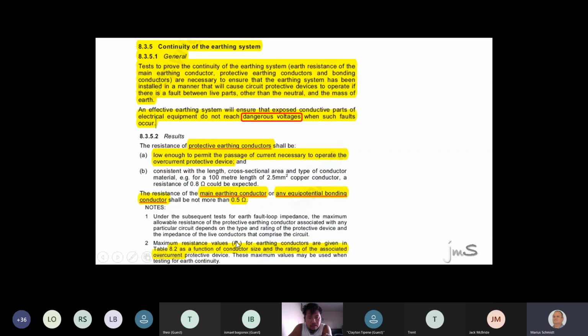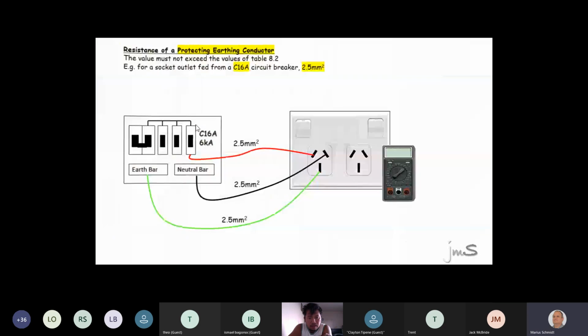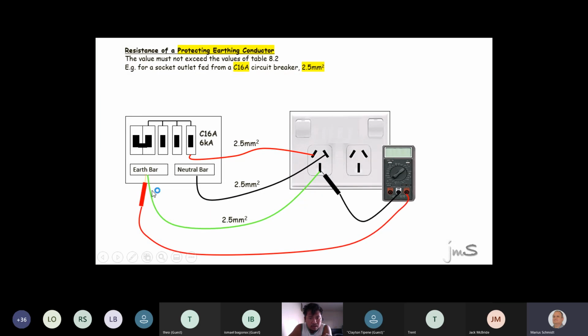If I ask you to do it on paper, can I confirm that I've got a red, a black, and a green going from a switchboard to a plug? You guys happy? How low is the resistance for that earth wire? What does the definition say? Low enough to operate the protection device if there was a short to earth. But how much ohms is low enough? Now, look, they can give you the table. What I'm going to do now, you all agree it's a C16 breaker. Can you all see that? You all can see it's a 2.5 millimeter cable.